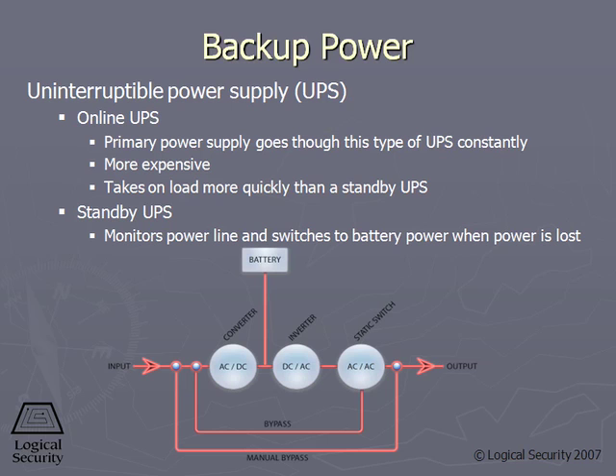We could have a loss of power for a brief moment, and when the battery switches in, it could introduce a spike on the line. Sometimes the interruption and/or the spike can cause your computers to fail or shut down. This can cause problems. The good news with the standby UPS is they're a little less expensive and they require a little less maintenance. In other words, the trickle charging of the battery doesn't destroy the battery as readily as the continuous power flow through the battery as with the online UPS.